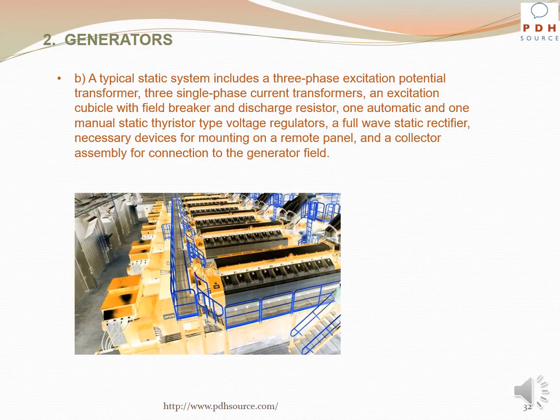A typical static system includes a three-phase excitation potential transformer, three single-phase current transformers, an excitation cubicle with field breaker and discharge resistor, one automatic and one manual static thyristor type voltage regulators, and a full wave static rectifier, necessary devices for mounting on a remote panel, and a collector assembly for connection to the generator field.